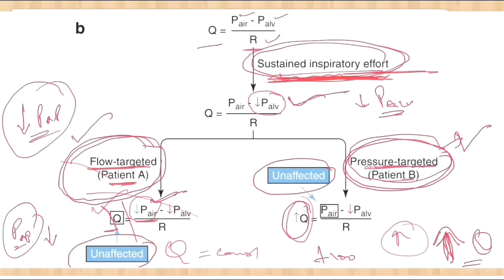Now in the second case, where we have patient B on pressure targeted mode, if there are sustained inspiratory efforts but the proximal airway pressure is constant, then what will happen to the flow? It tends to increase in order to keep this proximal airway pressure constant. Okay, so there will be an increase in the flow when there are sustained inspiratory efforts by the patient in case of pressure targeted mode. In case of flow targeted, there is a decrease in the proximal airway pressure. Clear?